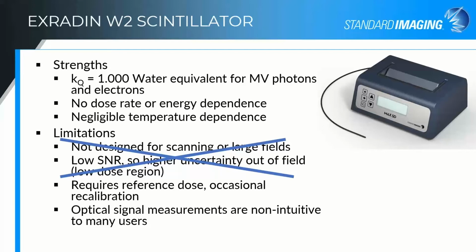It does still have the same properties of the scintillator. It requires that reference dose. It requires that occasional recalibration as you're using it.